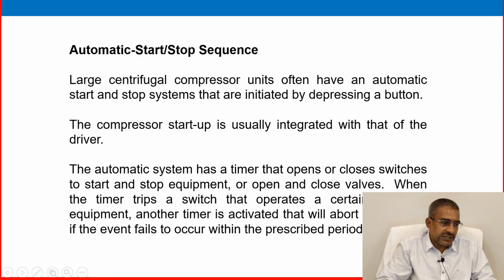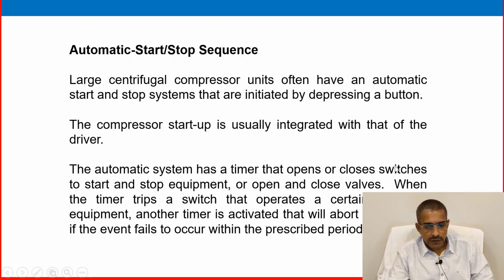So an automatic startup sequence is there in large or modern compressors, which means everything will be taken care of. We have to do some manual jobs like draining and other prior startup jobs and pre-startup checks. Then when we press the startup button, it will automatically configure and, in sequence, do all the pre-startup checks, and then the machine will start, the engine will start, then slowly the compressor starts after the necessary steps take place. But still we have to learn how to start and what the procedure for starting a compressor is; we have to read it if we get the opportunity.